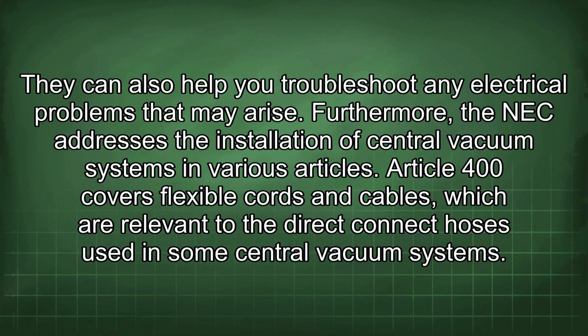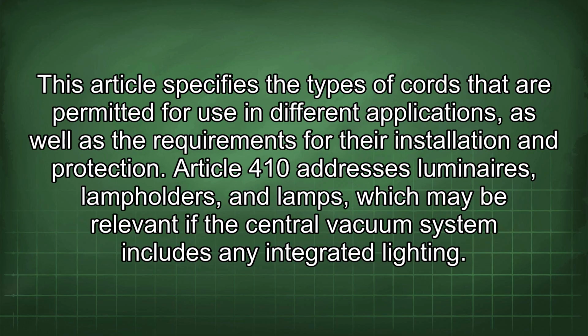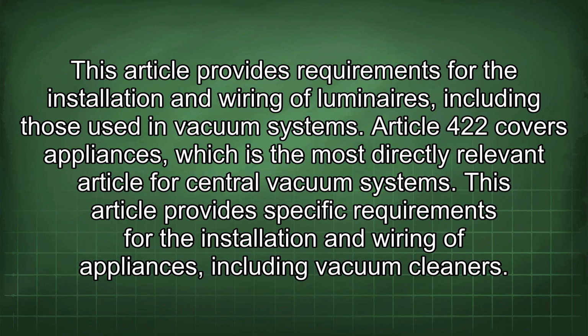Furthermore, the NEC addresses the installation of central vacuum systems in various articles. Article 400 covers flexible cords and cables, which are relevant to the direct connect hoses used in some central vacuum systems. This article specifies the types of cords that are permitted for use in different applications, as well as the requirements for their installation and protection. Article 410 addresses luminaires, lamp holders, and lamps, which may be relevant if the central vacuum system includes any integrated lighting. This article provides requirements for the installation and wiring of luminaires, including those used in vacuum systems.